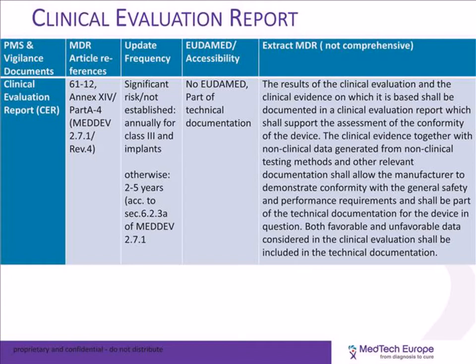There's a specific periodicity here on this report, which depends on the risk classification of the device. For class 3 and class 2 and implants, we have an annual production of these reports. And for the other classes of device, less risky device defined by their classification, this is a 2 to 5 years production and update of this CER.